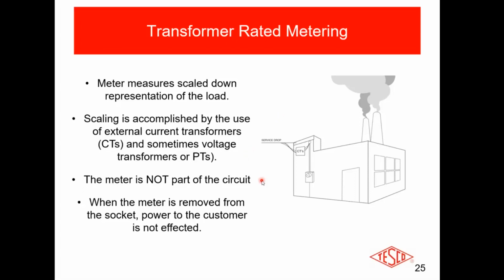You use your test switch, you bypass the meter circuit, and now you can remove the meter, you can clean up the socket, you could replace the socket, you could test the meter, you can test the transformers, you can do anything that you want to do there. All right? So that's the very basics of transformer-rated metering.